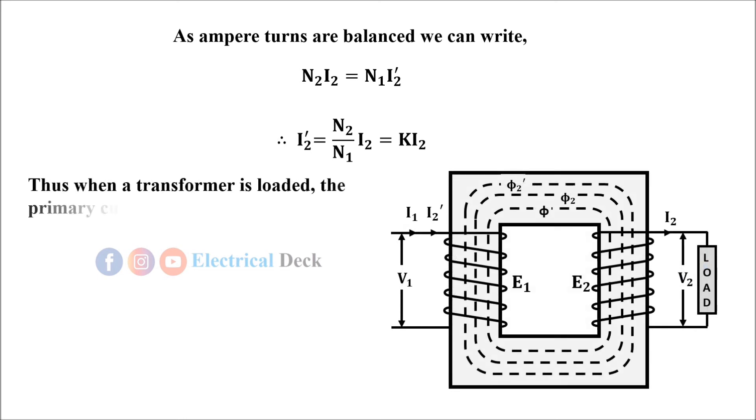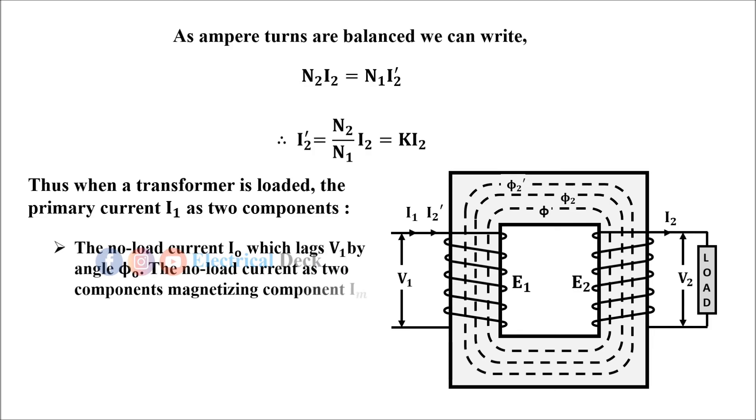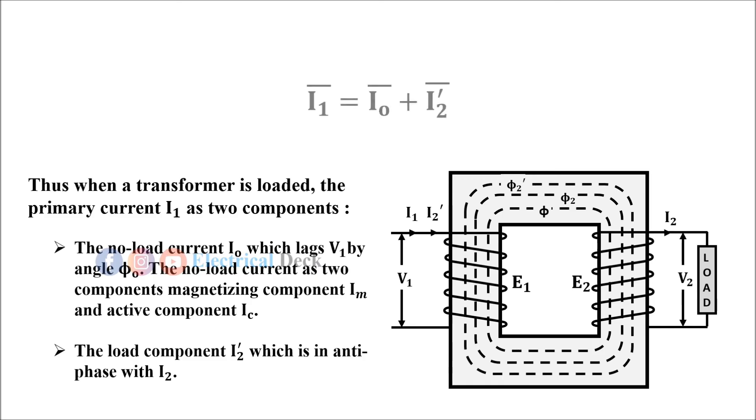Thus when a transformer is loaded, the primary current I₁ has two components: the no load current I₀ which lags V₁ by an angle φ₀, with magnetizing component Im and active component Ic; and the load component I₂' which is in antiphase with I₂. Hence the primary current I₁ is the vector sum of I₀ and I₂'.